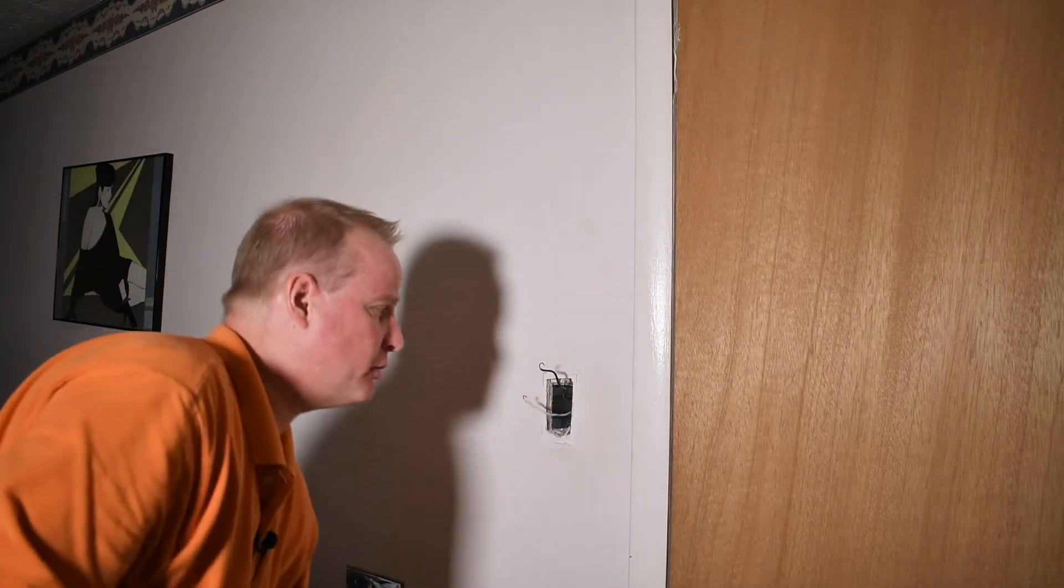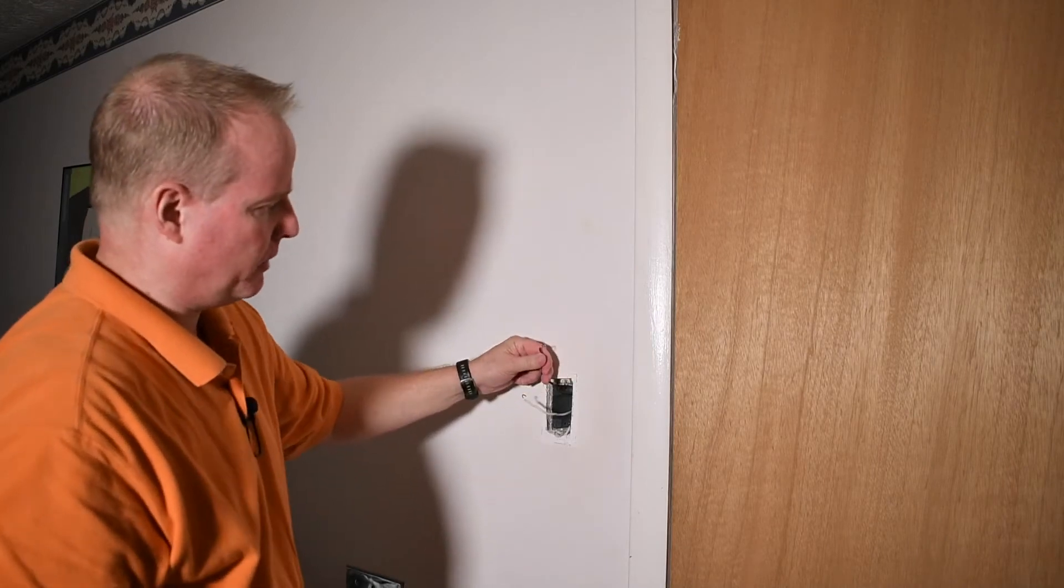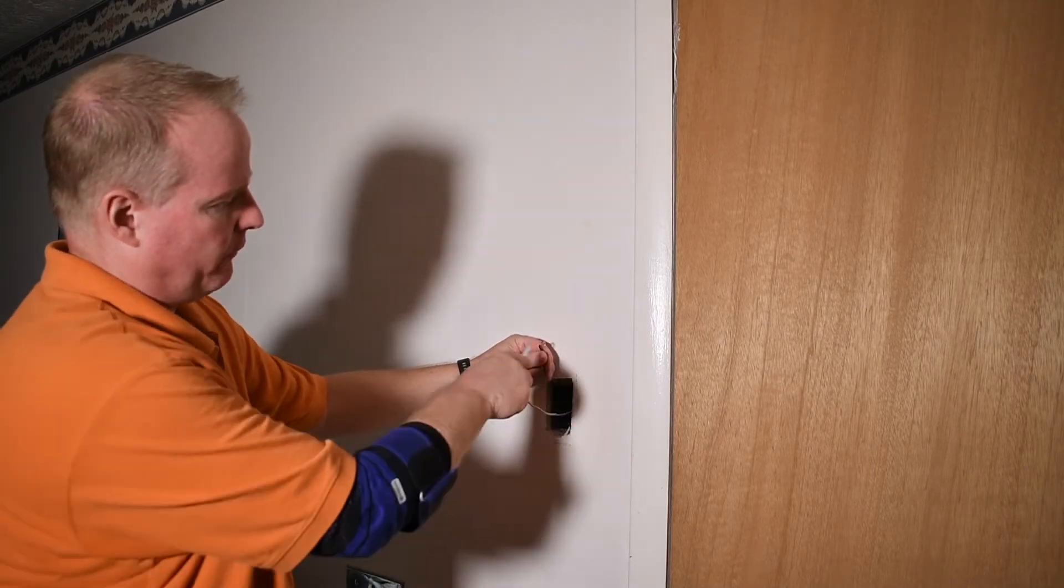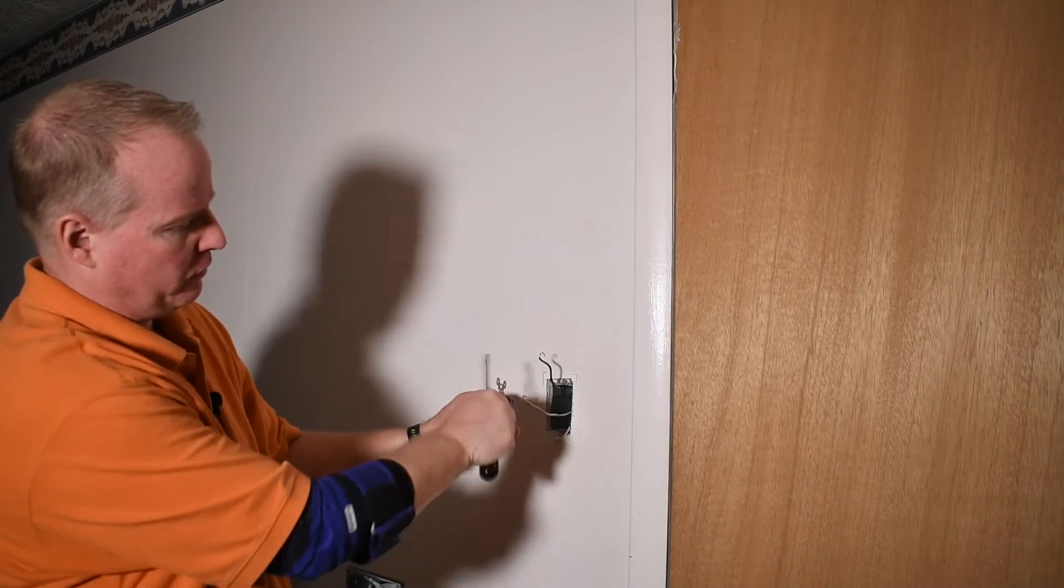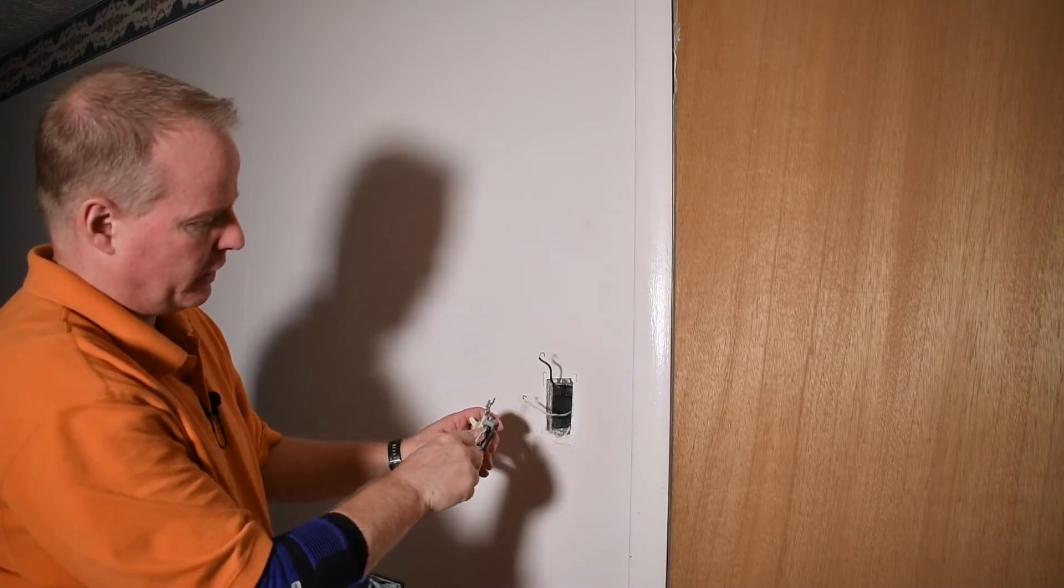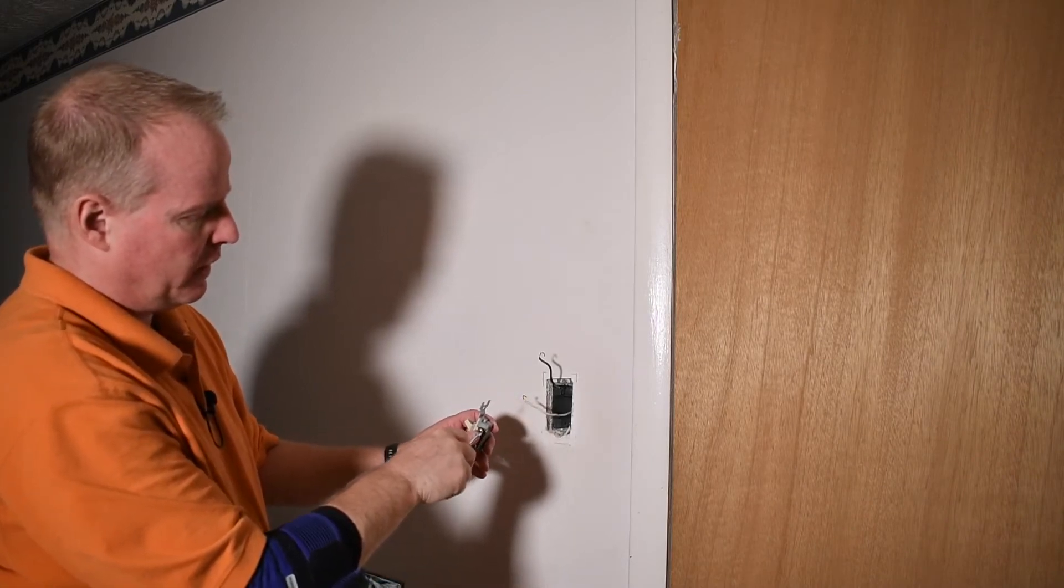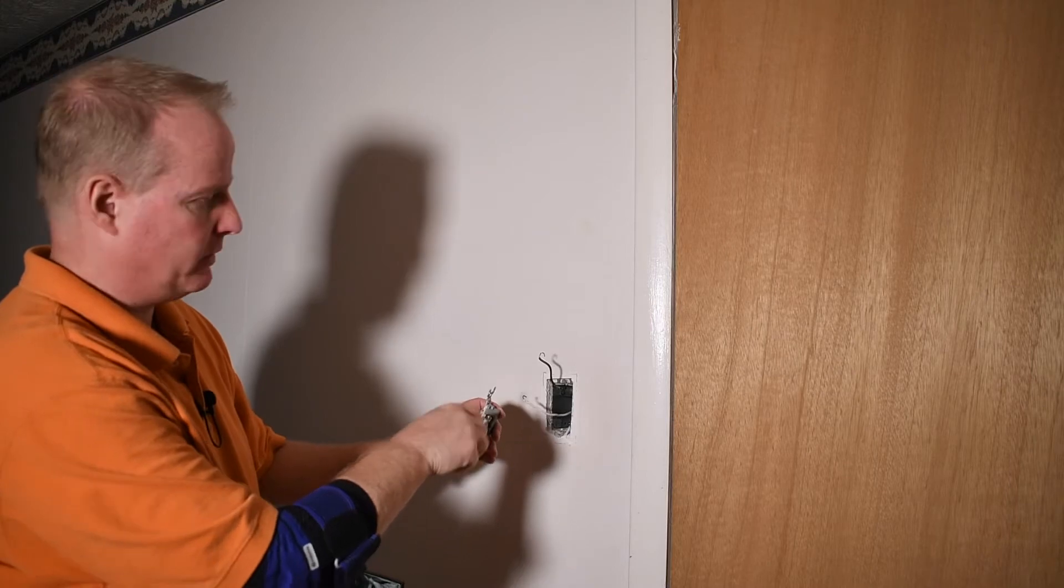Older outlets were generally installed with this little pigtail method. If you do a pigtail using these screws, make sure you wrap the pigtail clockwise around so as you tighten the screw up at the end, it actually draws the pigtail even tighter.